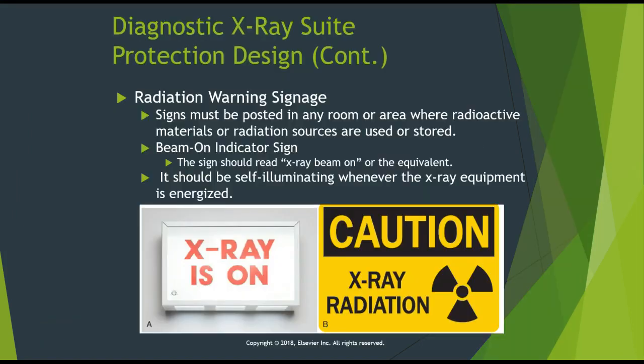Okay, and lastly, we are done. Lastly is X-ray signage. You have all seen these signs, but they are necessary. It is required in an imaging suite. This is part of your radiation protection. Signs must be posted in any room or area where radioactive materials or sources are used. The beam on indicator sign must be on when an exposure is being made. It must be self-illuminating when that equipment is energized. Therefore, if you're paying attention, you should never be walking into an X-ray room when an exposure is being made.